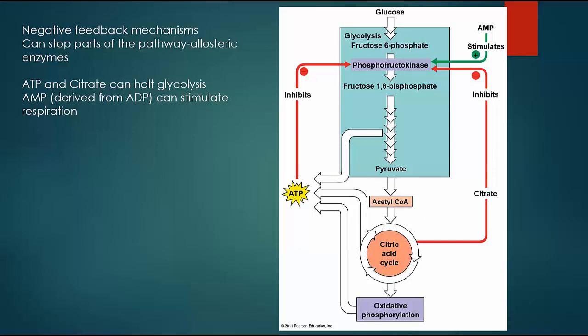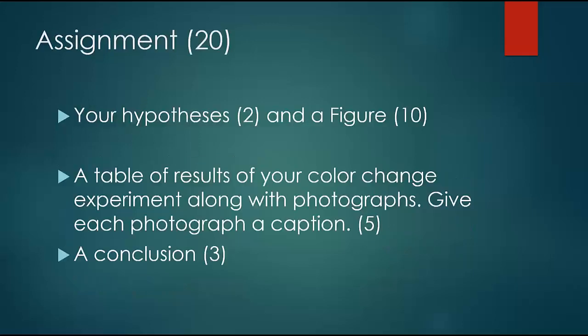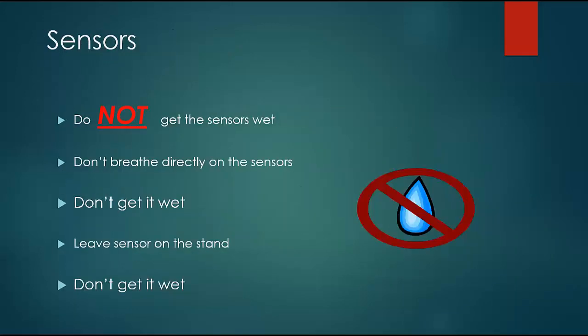A few tips about the probes this week: do not get the sensors wet - they're really expensive and they break when wet. Don't breathe on the sensors, don't get them wet, leave them in the stand whenever possible (which is probably the entire lab). One thing I should tell you before I move on is, in between runs, if you have a lot of CO2 accumulated in the sensor you can use a fan to blow the sensor out - just leave it in the stand and blow air across the sensor to return it closer to ambient levels of carbon dioxide.